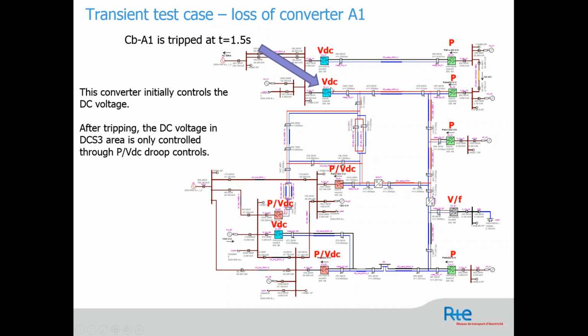So here, of course, this is a station which controls the VDC. When you use a VDC, what do we expect? We expect that the P control here, since it controls the P control here, will not change and will not have any effect. And here, when you have a droop control, PVDC, in this case, this station will drop because you will lose some power here. So this one will automatically adapt as a primary control to adjust the VDC with respect to the active power, as we will see in the next slide.